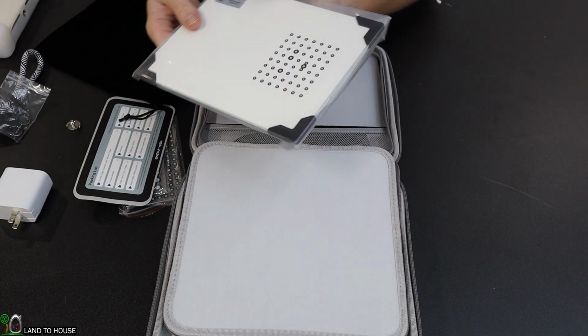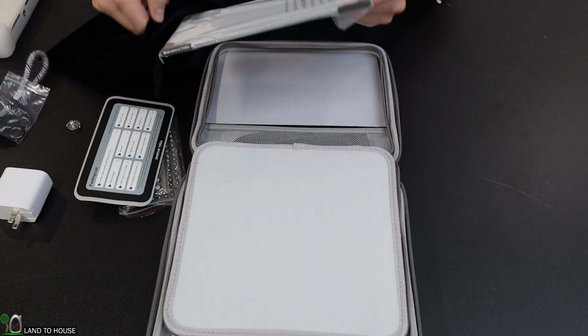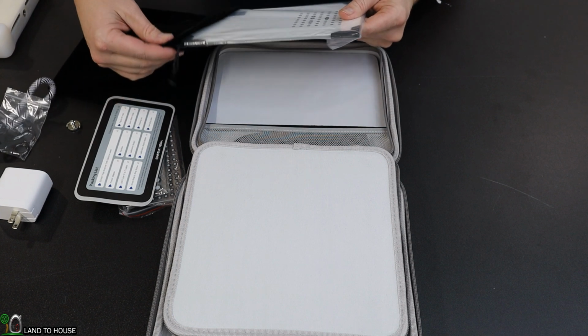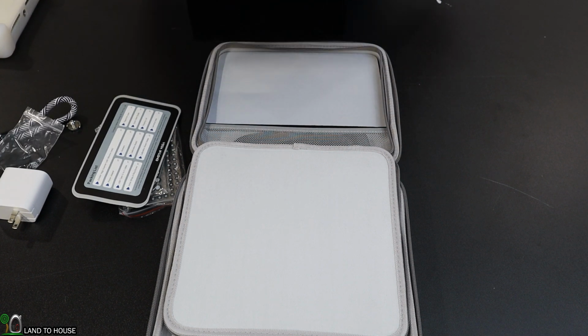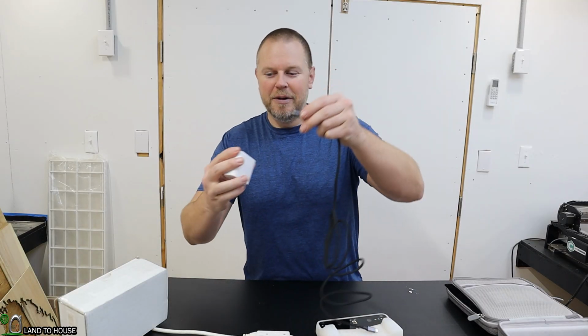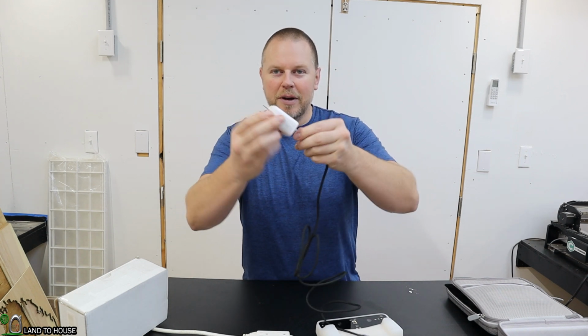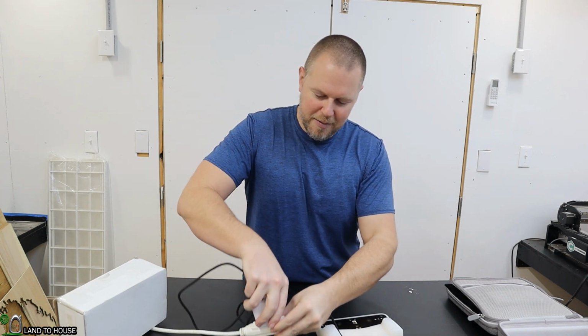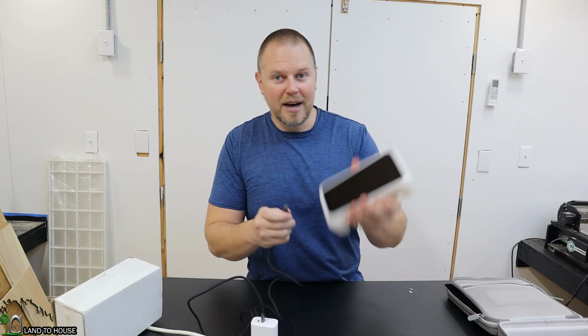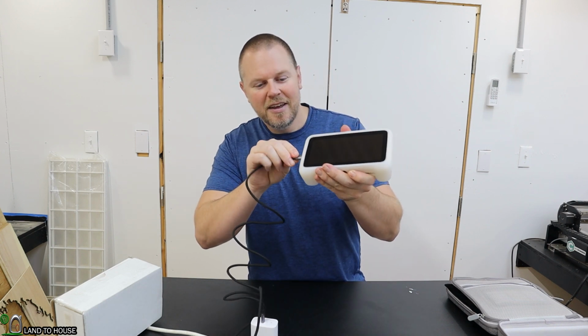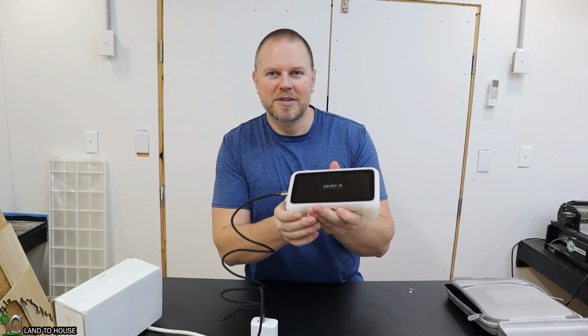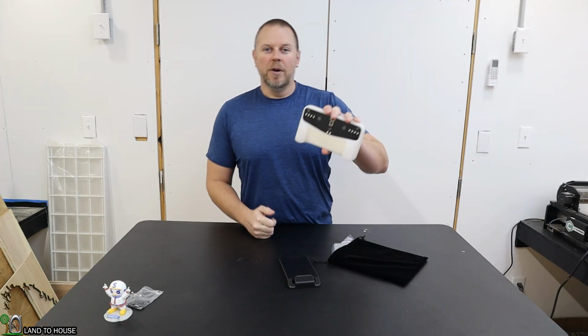We will have to calibrate. I believe it's important to calibrate fairly often with this scanner, so we will go through that process here in just a moment. For step number one, I'm going to charge this unit. So I've got the USB-C adapter, going to plug this up to my grid power, and then plug this up on the side and let this charge up to 100%. The scanner is now charged to 100%.